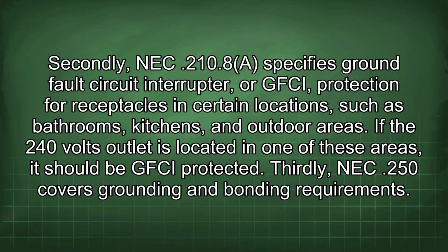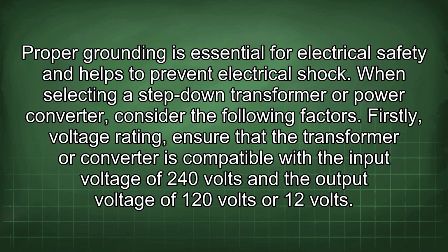Secondly, NEC 210.8 specifies ground fault circuit interrupter, or GFCI, protection for receptacles in certain locations, such as bathrooms, kitchens, and outdoor areas. If the 240 volts outlet is located in one of these areas, it should be GFCI protected. Thirdly, NEC 250 covers grounding and bonding requirements. Proper grounding is essential for electrical safety and helps to prevent electrical shock.